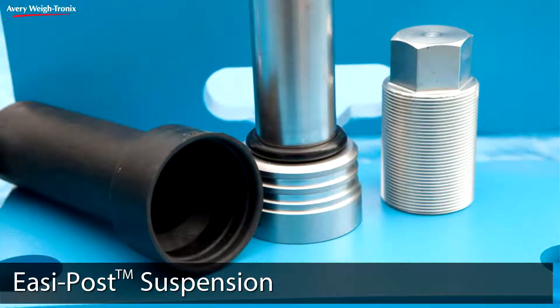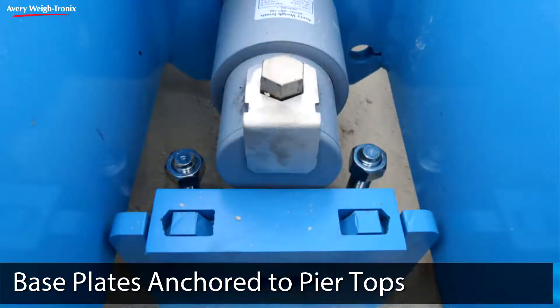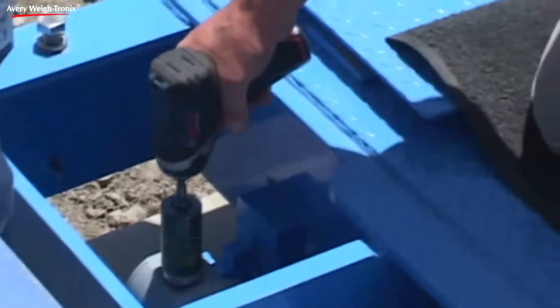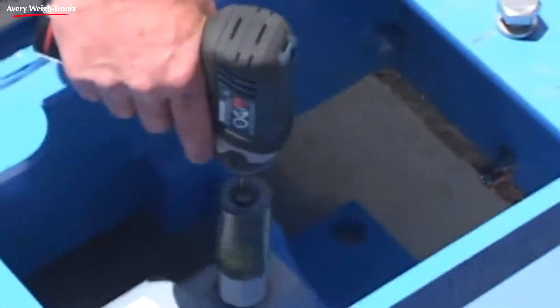The Easi-Post suspension system further reduces installation time, with base plates anchored directly to pier tops requiring no grouting. Unevenness in the scale foundation can be quickly and easily compensated for with simple height adjustment screws instead of shim plates.